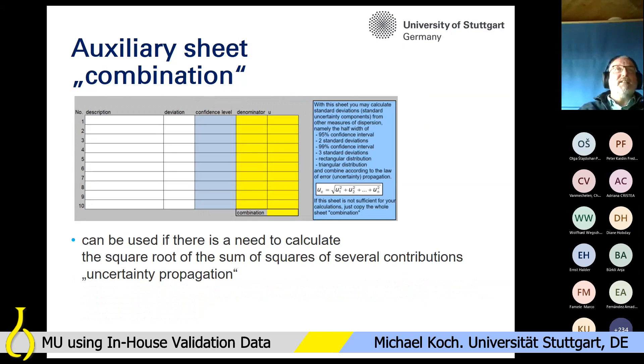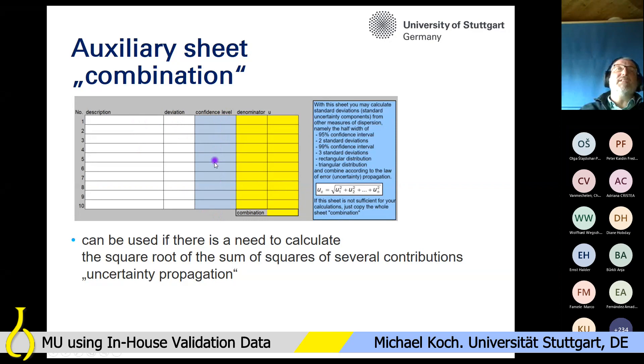Finally, there is another auxiliary sheet called 'Combination.' This can be used if you need to calculate the square root of the sum of squares of several contributions — essentially a small uncertainty budget. You can enter confidence intervals at different confidence levels: one sigma, two sigma, three sigma, 95%, 99%, rectangular, or triangular, and the sheet calculates the standard uncertainty and combines them.